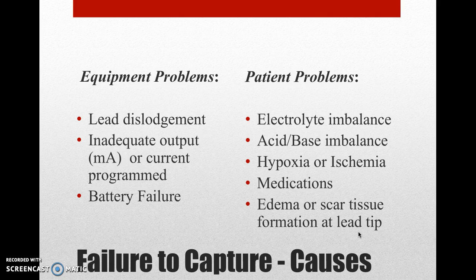Failure to capture has different causes. Some causes are equipment related, such as lead dislodgement, inadequate current or MA, or battery failure. It can also be patient related, such as electrolyte imbalances, acid-base imbalances, hypoxia or ischemia, medications, or edema and scar tissue formation at the lead tip.